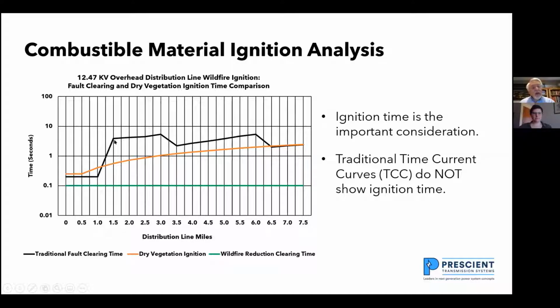Between mile 1 and mile 1.5, this is where time overcurrent relays are going to operate. At mile 3, this is where a recloser starts operating. And at mile 6.5, that's another recloser. So the clearing time that I'm showing here for faults on the black line, this is assuming that I have the standard protection schemes today, where I have a fault, I trip, I reclose. If the fault is still there, I trip again. I reclose, I trip again. If the fault is still there, so I have 4 trips and 3 closes, that is the standard trip close cycle on an overhead distribution line.